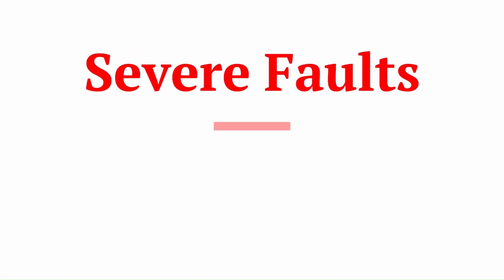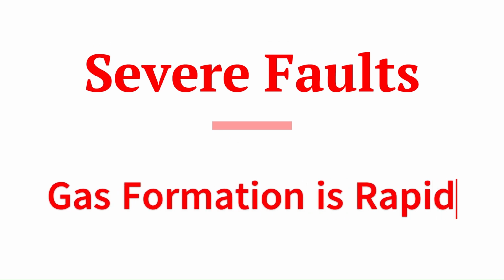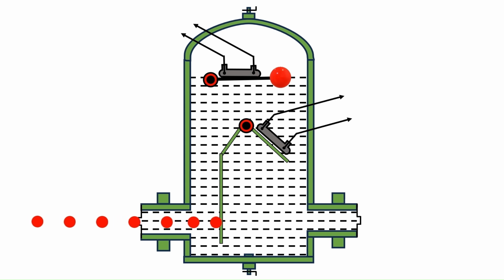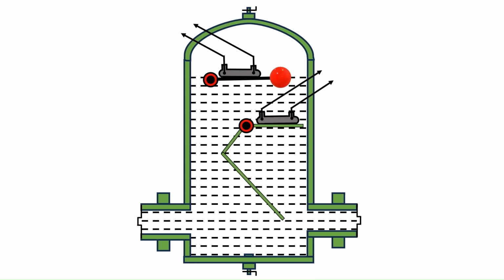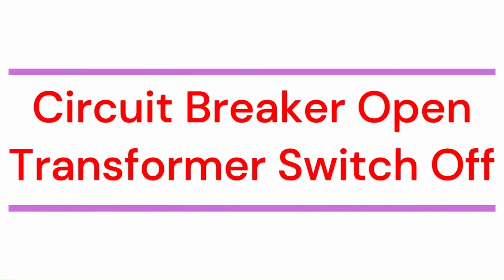In case of severe faults, gas formation is rapid and a large amount of gas rushes from the transformer to the Buchholz relay. During its travel, the gas produces sufficient pressure on the flap, so the flap turns in the anti-clockwise direction. The mercury switch also tilts and the mercury level inside the mercury switch shifts, which will close the trip circuit contacts. Therefore, a trip signal is produced which causes operation of the circuit breaker. Circuit breaker will open its contacts and the transformer will switch off.